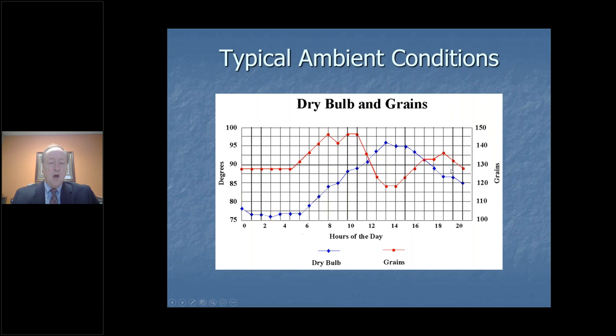This might be a typical day for you, not a rainy or stormy day, but just a cycle. On this particular day, this was the moisture level we were reading. This was the grains of moisture per pound of dry air, the absolute moisture. And we see it was somewhat steady during the night, and then it began increasing during the mornings. This was 8 o'clock in the morning, and then again at 10 o'clock and 11 o'clock. And then for some reason, it dropped down. Maybe there was a wind, a cold front coming in, or at least a cool front or a dry front with the winds blowing. But we see a cycle like this. I'm not telling you that every day looks like this, but I want to point out that the dry bulb peak and the moisture peak are not necessarily coincident peaks. You might very well have an extremely humid morning and then it tapers off in the afternoon.